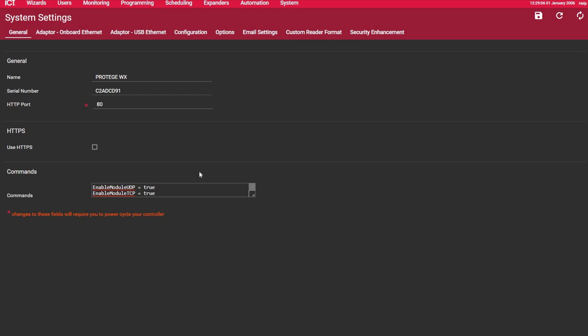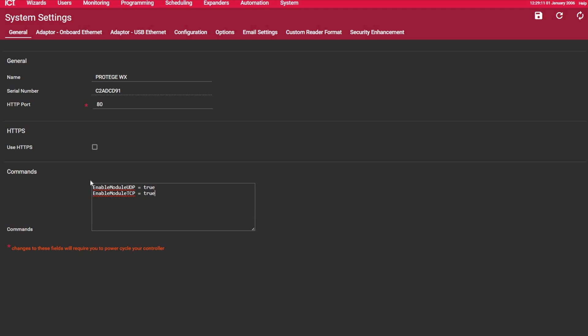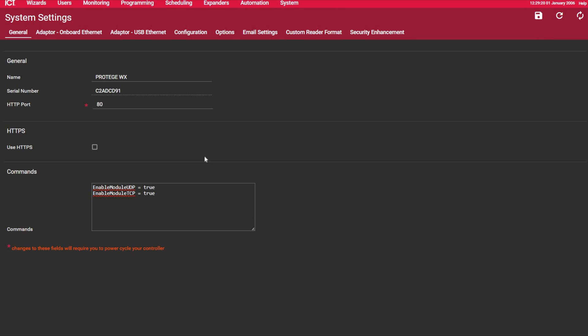Let's have a look at the WX interface. To give you an example, if I had on this site an entry station and an MNR2, these will be the commands to use. I found this in the system page and then system settings. You can just save them and then the controller will open those ports so that the modules can communicate with it. It's good for the entry station to connect with the SOAP service of the WX or GX, and also in this case for an MNR2 to allow a communication channel with the GX or WX controller.